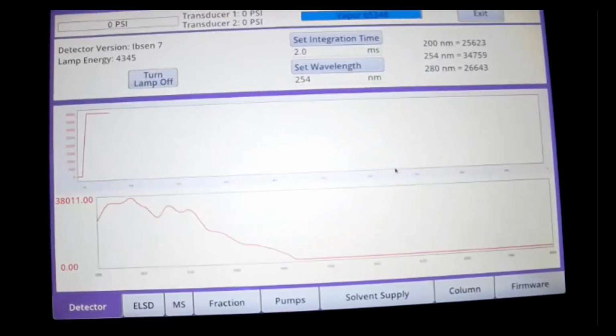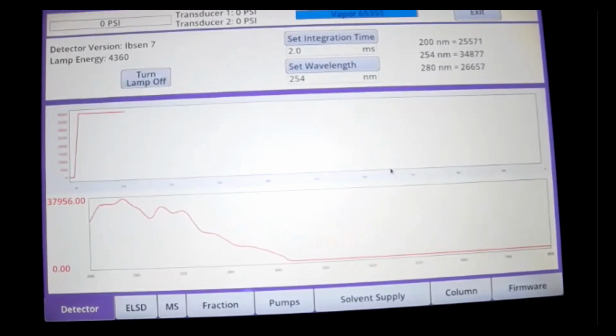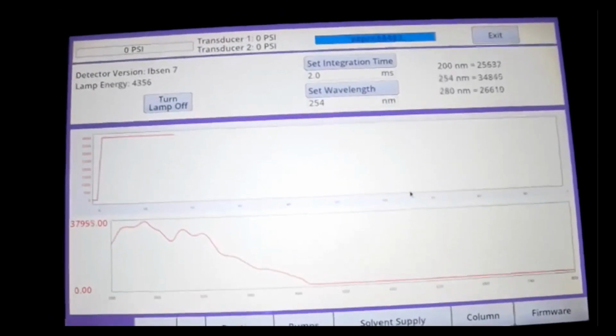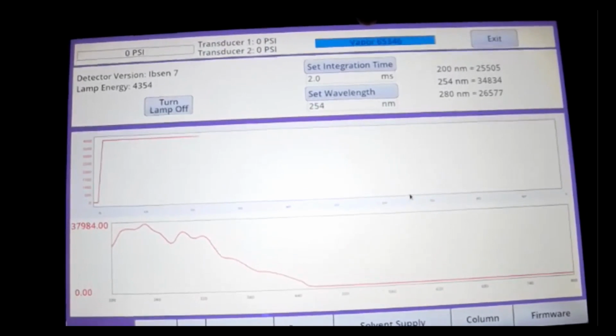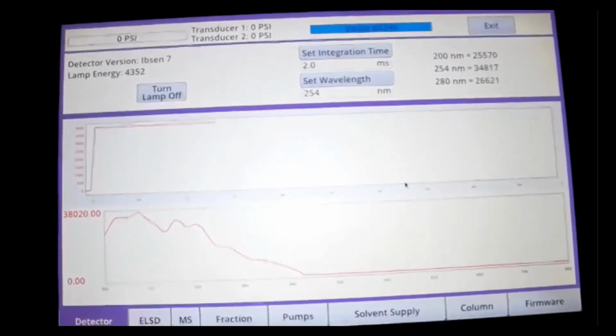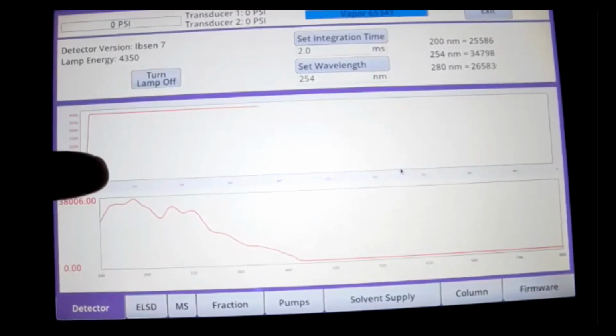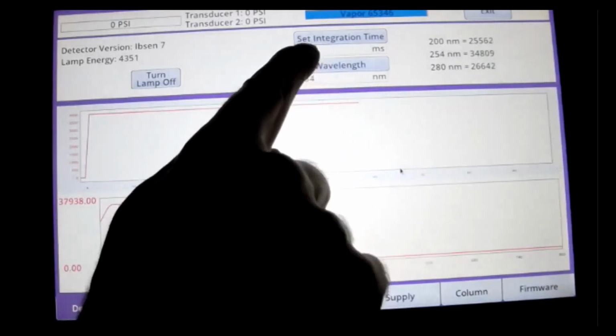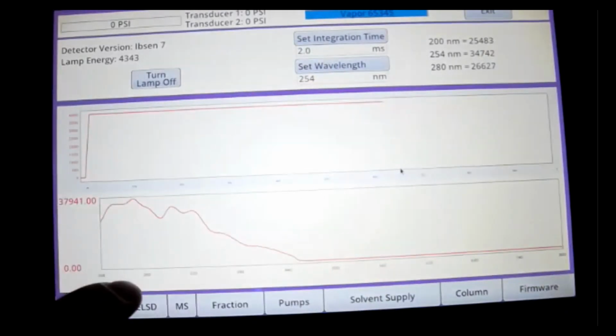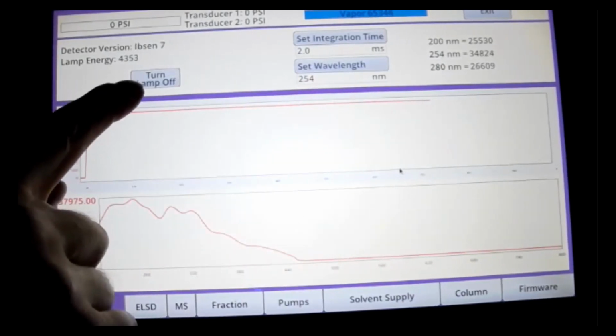All right, so it takes you to the detector screen to start. And something you'll notice here kind of at the top, vapor. I don't have a vapor sensor installed, so it's maxed out. Don't worry about it. It's fine. But here's where I was talking about. You can turn the lamp on and off. This is actually a graph showing you what the light intensity is. And so I have my integration time up here set to 2. Okay, my wavelength is set to 254. I can turn my lamp off if I want to, but it's giving me a lamp energy reading.